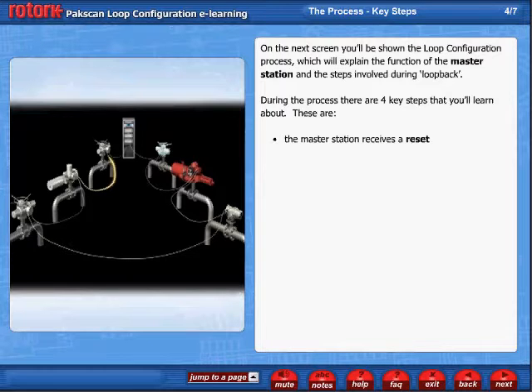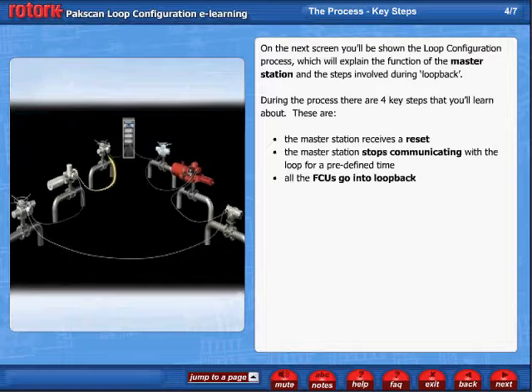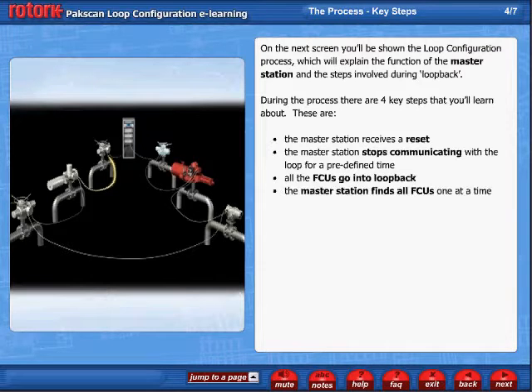These are: the master station receives a reset; the master station stops communicating with the loop for a predefined time; all the FCUs go into loopback; and the master station finds all FCUs one at a time.